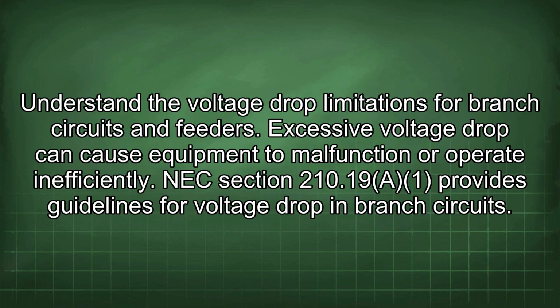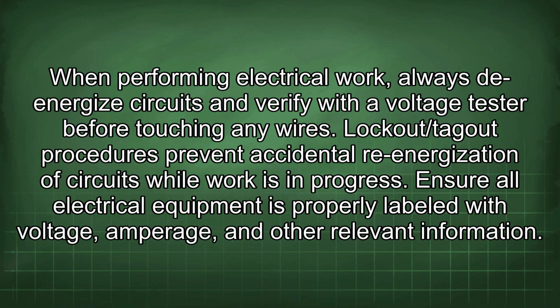Understand the voltage drop limitations for branch circuits and feeders. Excessive voltage drop can cause equipment to malfunction or operate inefficiently. NEC Section 210.19 provides guidelines for voltage drop in branch circuits. When performing electrical work, always de-energize circuits and verify with a voltage tester before touching any wires.